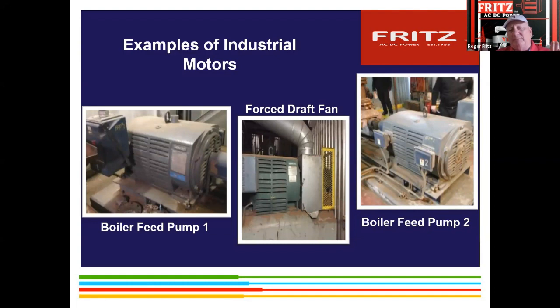Well, by regulating the speed up to about 62, 63 Hertz, they were able to get the extra amount of water that they really could use at the boiler. And it actually increased the output of the plant by almost another 0.5 megawatt. That simple adjustment did it. And then by the time they put drives on all the other parts of the facility, they saw about another $500,000 worth of savings, just on all of the other ancillary fans, pumps, and stuff that it takes on a power plant.